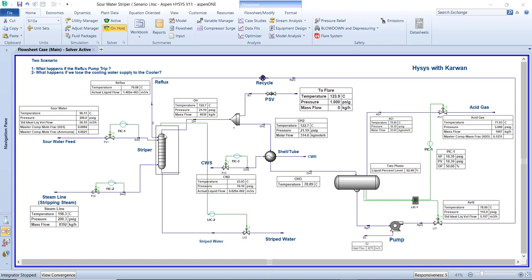At the top of the tower, we strip out the H2S, ammonia, and some losses. This overhead goes to two points. Before going to the separator, we have to cool down the temperature of the top of the tower, because the top is totally in the vapor phase. The temperature there is 122°C. H2S and light hydrocarbons stay in gas phase, ammonia is also in gas phase, and water is in vapor phase.